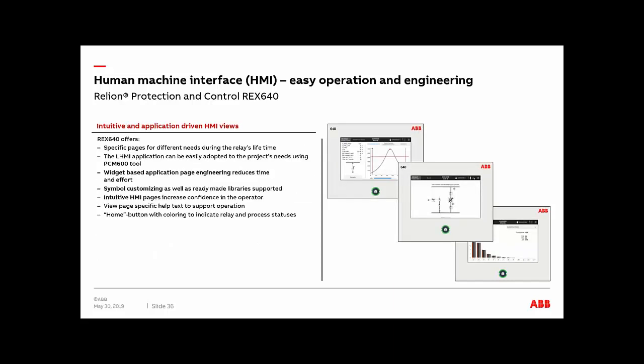So you're going to have specific pages for different needs during the relay lifetime. Like I said, we're going to provide some pages, but you could configure additional pages, and that depends on your specific application. You got a wide range of ANSI and IEC symbols. You got push buttons that could be configured on the front of the HMI. As you can see, there are no physical push buttons on the relay, but you could virtually program push buttons and have a screen where you can display them and use them for different control functions or logic functions for that matter. Blocking or protection, different shortcuts can be implemented as well in the HMI.